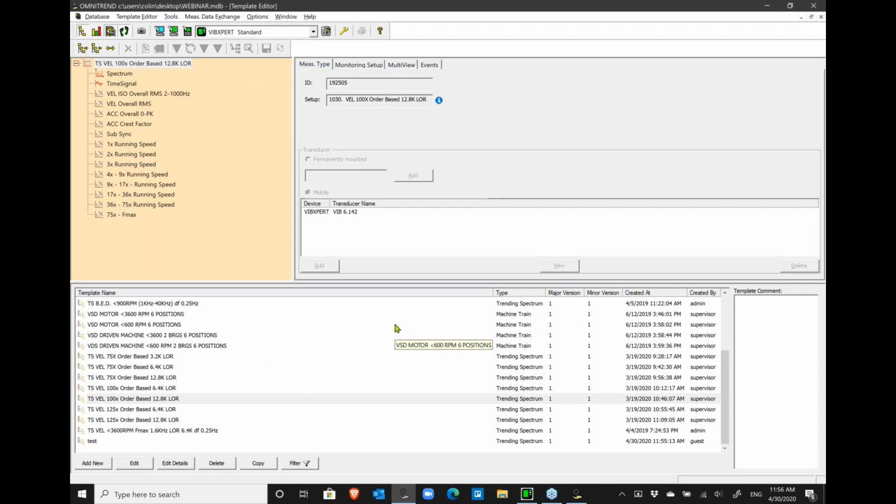Now, obviously, we're coming to the end of our hour of webinar. It's been a pleasure to show people around OmniTrend software again and answer some of the questions. One of the common ones that we didn't get to is, why have my readings changed so they are now 5 times higher? Well, that's one that happens a lot when people use the wrong sensor. You have to make sure you use a 6.142 sensor with the PRUFTECHNIK VIBXPERT. If you use a 6.147, it amplifies them all by a factor of 5. That's a common one that we get into tech support.